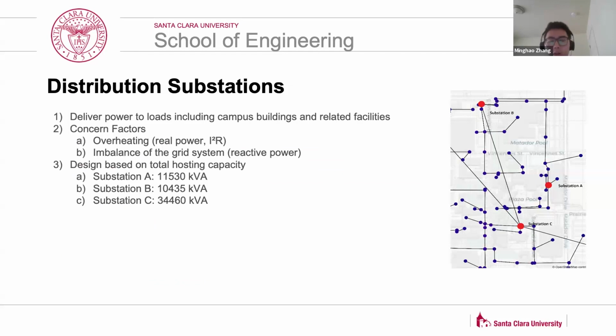In the analysis, two main factors are considered to run the PV and storage system safely in the network. First is overheating caused by the real power, and the second one is the imbalance of the three-phase network caused by reactive power. We design our system based on the following regulated hosting capacities for each substation. Let us move on to the next slide, please.